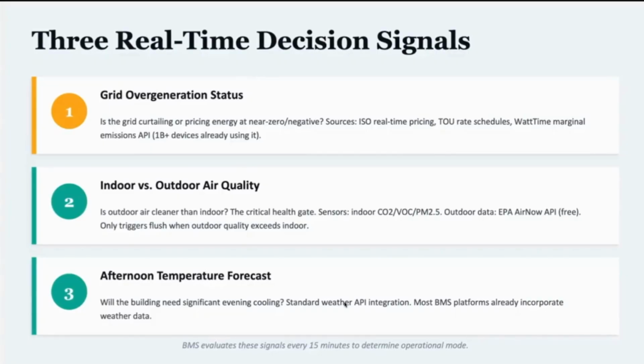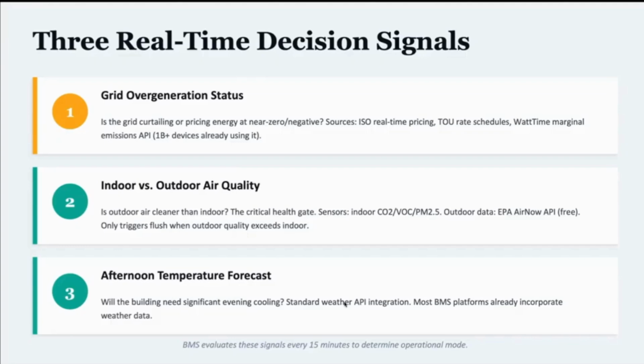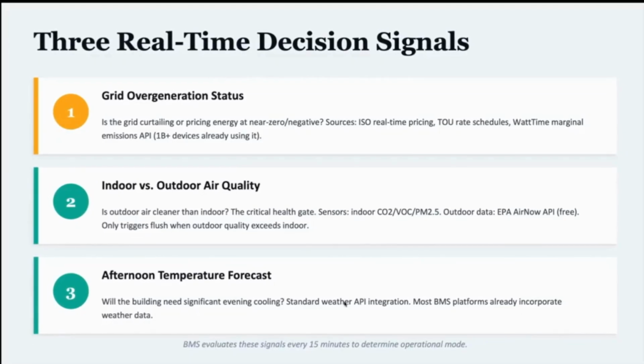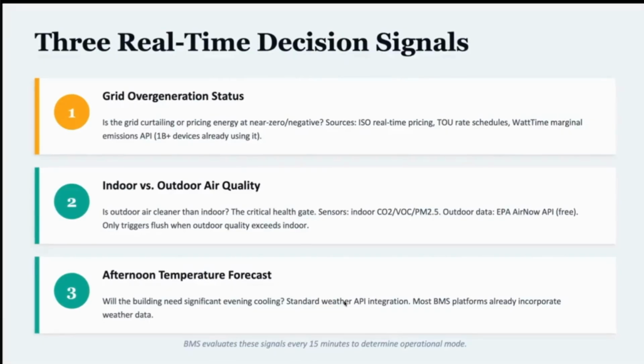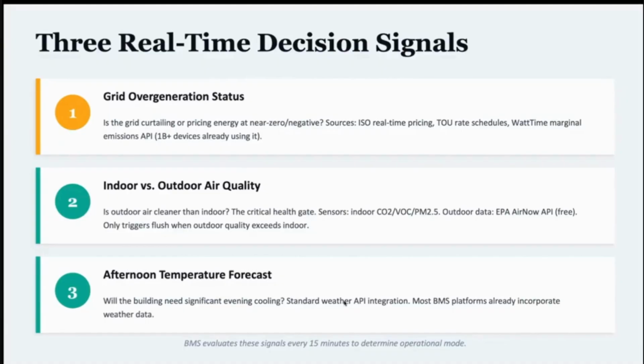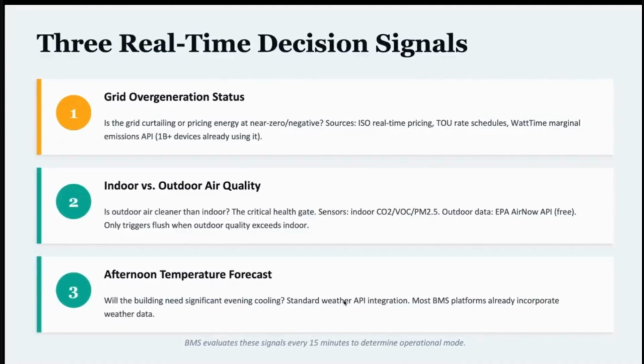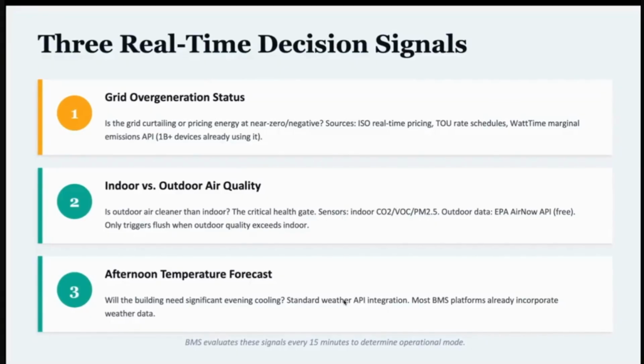Should we run the air ventilation and flush the air during this time? And then third is, based on the temperature differentials and the forecasted demand for cooling the building later that day, does it make sense to pre-cool the building during this window of time when we have surplus solar that we can use to do that work and basically help reduce the ventilation or cooling demand later in the day.